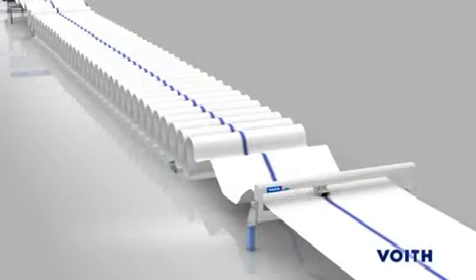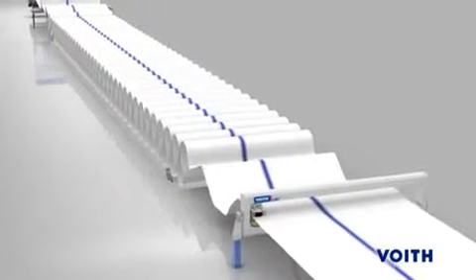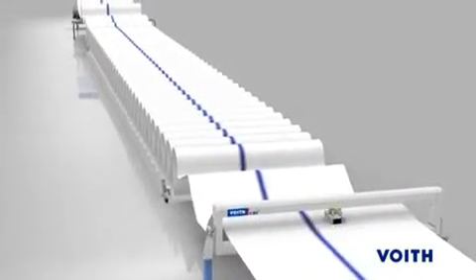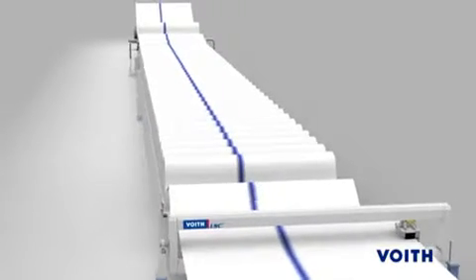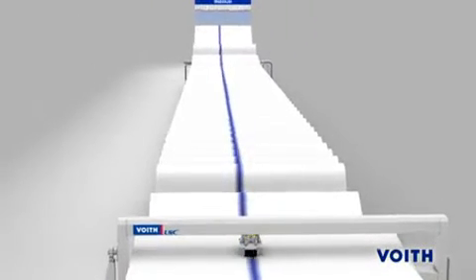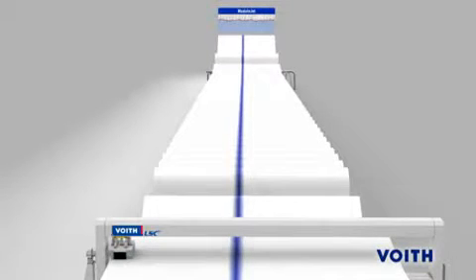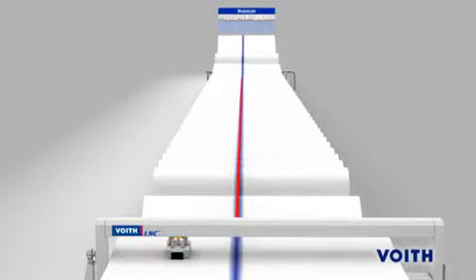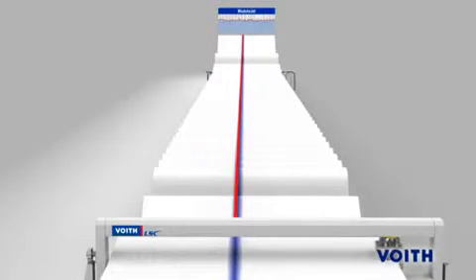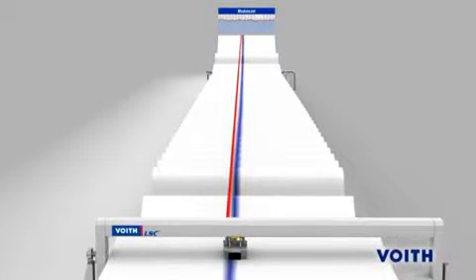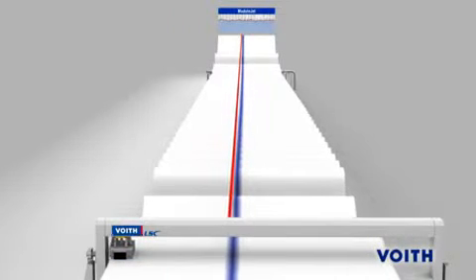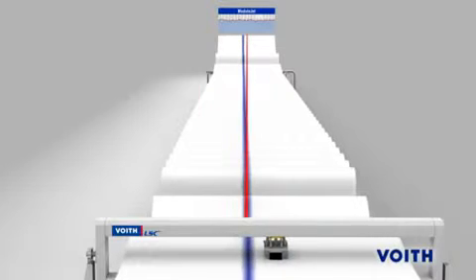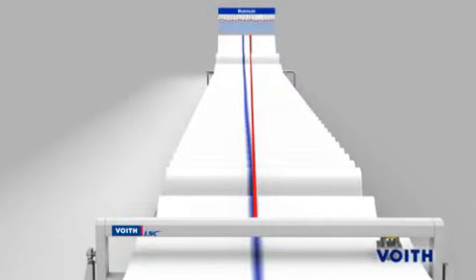Until the paper has run a few hundred meters through the machine, web shrinkage and web wandering can result in the measurement point and the actuator position not being exactly in line. For strong deviations, as shown here in an exaggerated way, simple control systems would activate the wrong actuator, thus creating a new profile deviation.